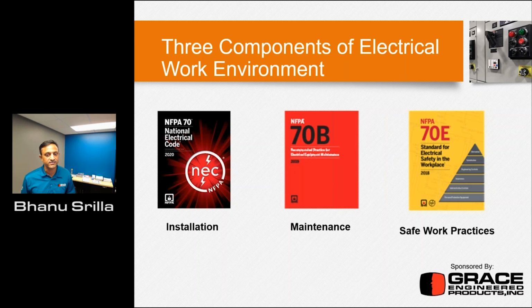So if you look at NFPA 70E alone, NFPA 70E calls out specific areas. There is a callout to NFPA 70B, which is the maintenance standard, the recommended practice for electrical equipment maintenance, and also to the installation code, which is NFPA 70, or the NEC.